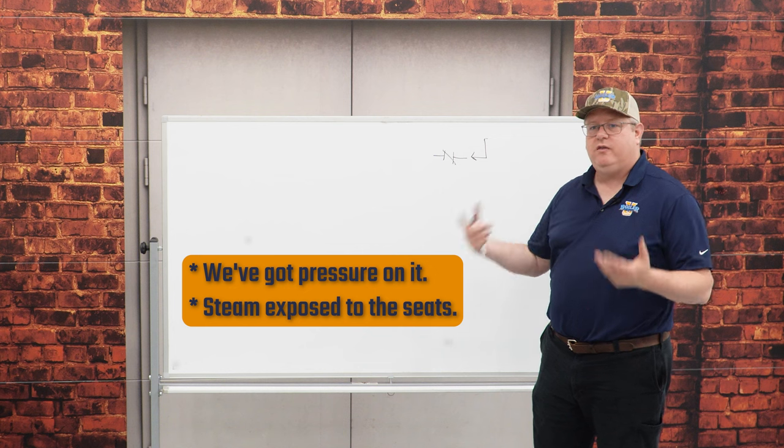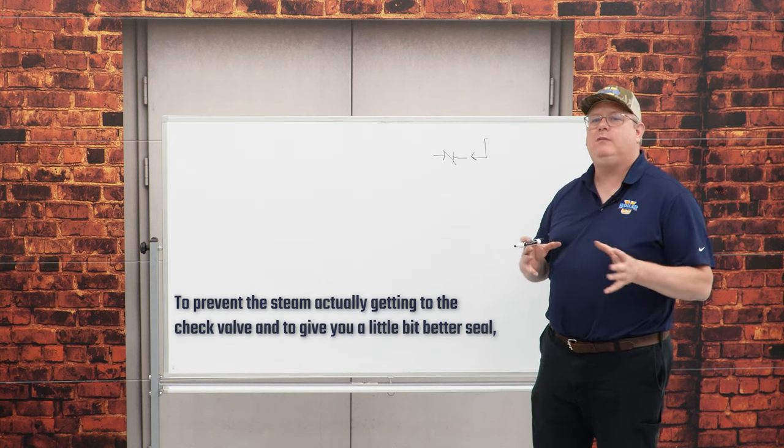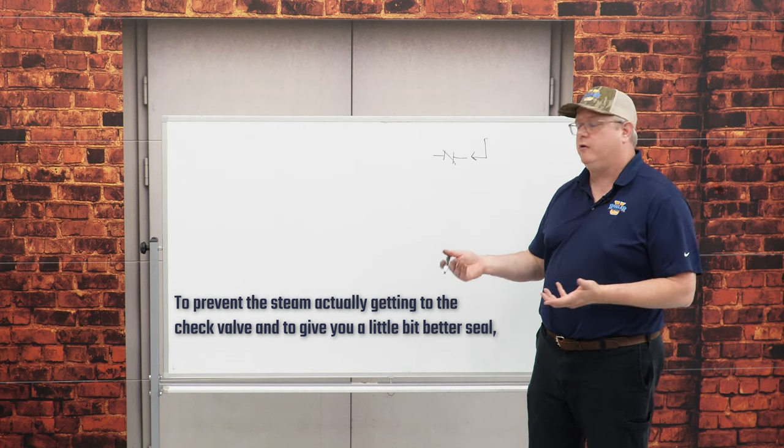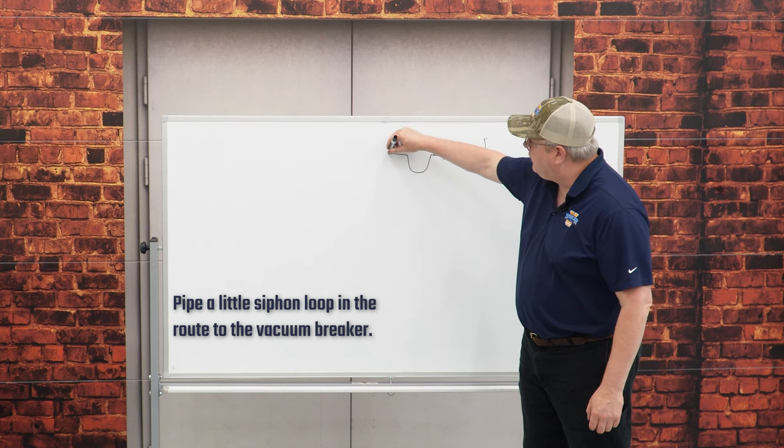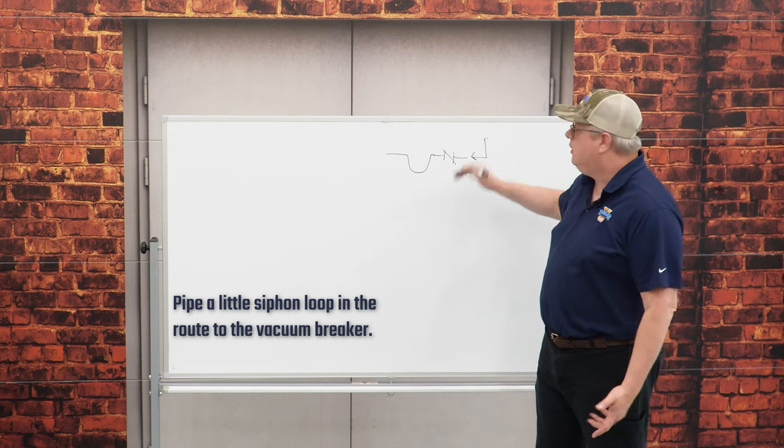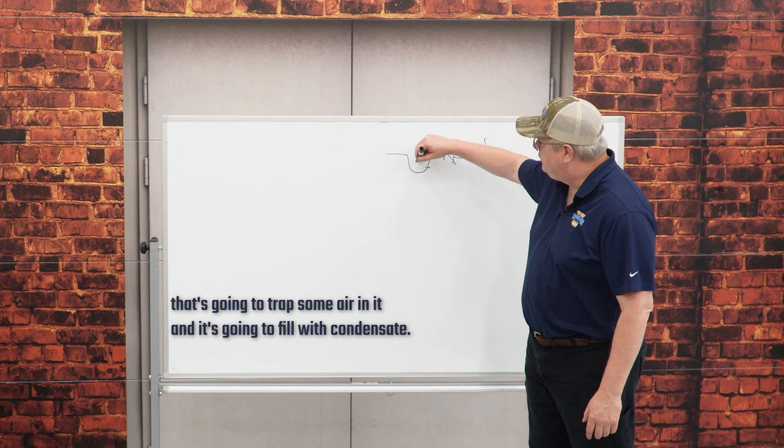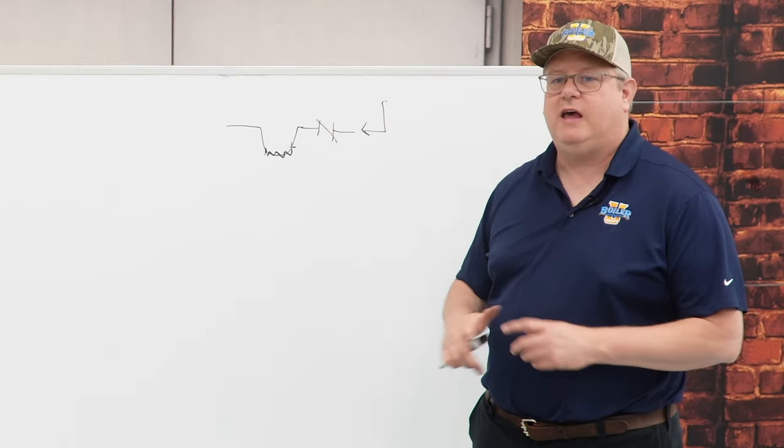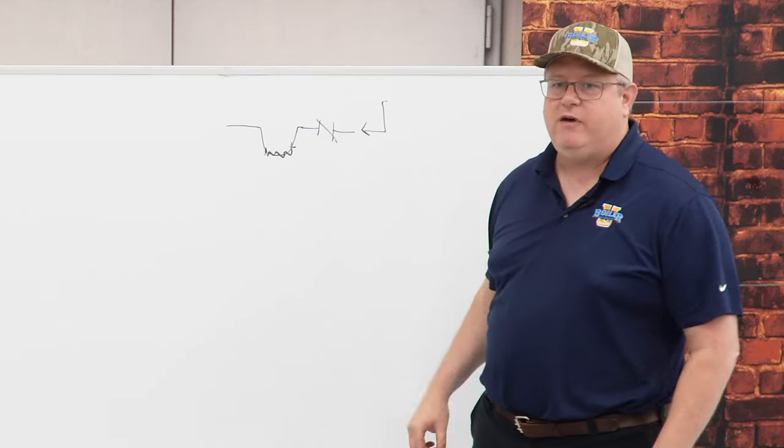So to prevent the steam actually getting to the check valve and to give you a little bit better seal, you can actually pipe a little siphon loop in the route to the vacuum breaker. What that will mean is when we start up, that's going to trap some air in it and it's going to fill with condensate, so we're much less likely to have rapid deterioration of that vacuum breaker check valve.